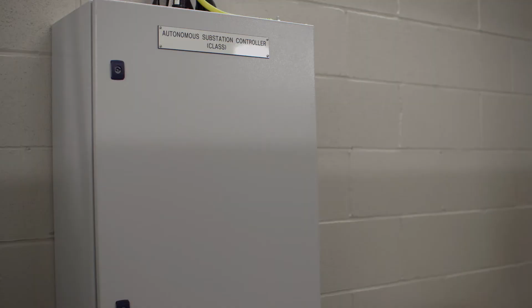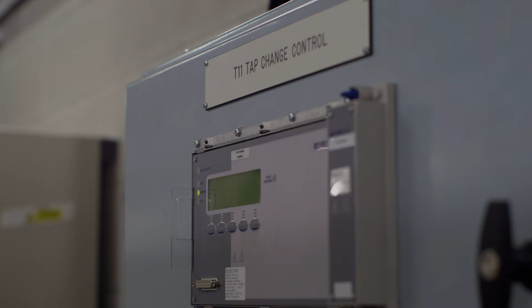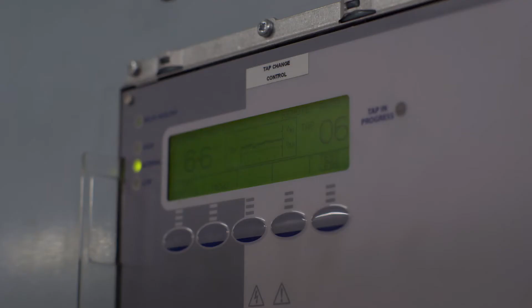As part of the CLASS project, we use a device we refer to as the ASC, which stands for Autonomous Substation Controller. It's literally a box on the wall, and its job is to take commands from our remote control system, the way we normally operate the network from our control centre, and it's designed to change values on the tap change control relays, which change the voltage to customers on the system.